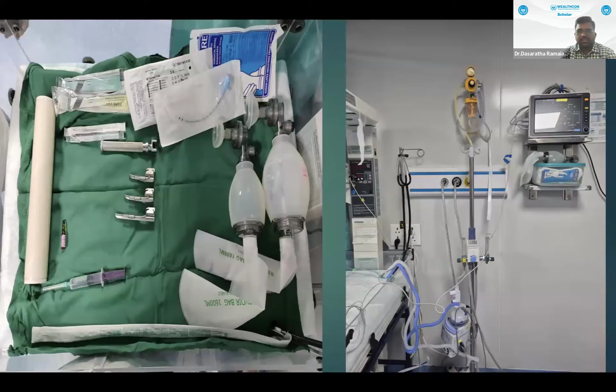The most important step in the equipment check is testing the self-inflating bag. The 3 ways to check the self-inflating bag: squeeze the bag and feel the pressure against your hand; block the mask or gas outlet and squeeze the bag to see if the pop-up valve is moving; and by closing both mask and valve, look for a leak. We'll see both a normal self-inflating bag and a self-inflating bag with a leak with demonstration.